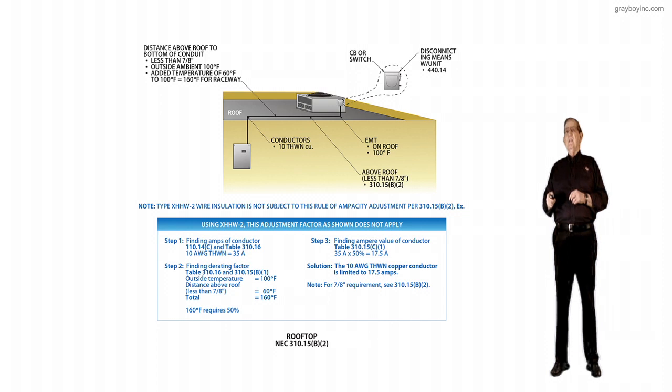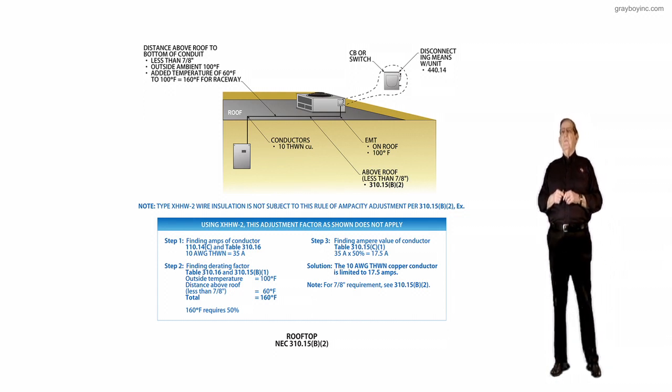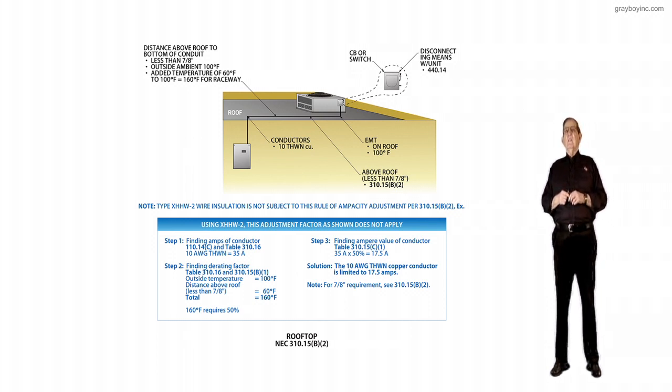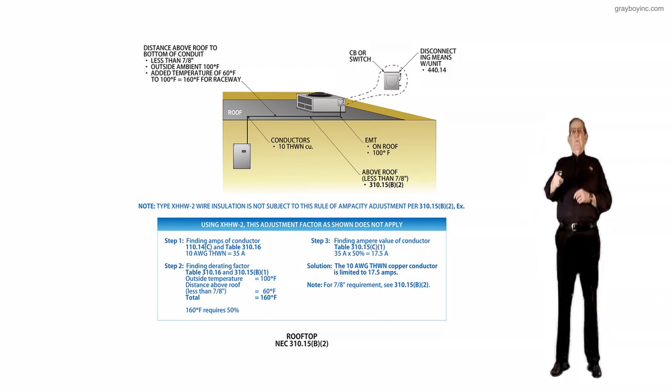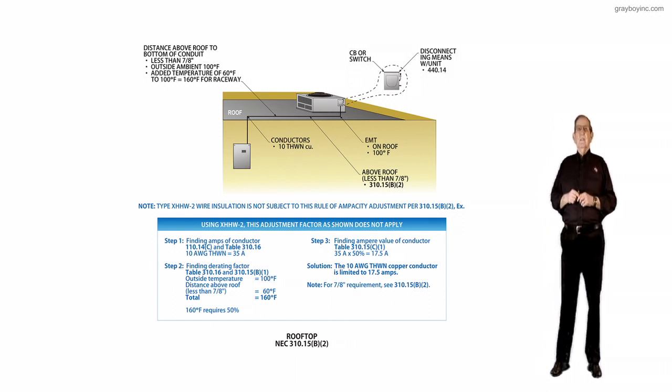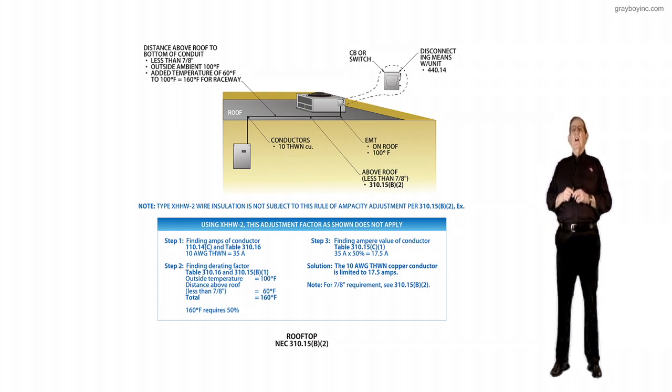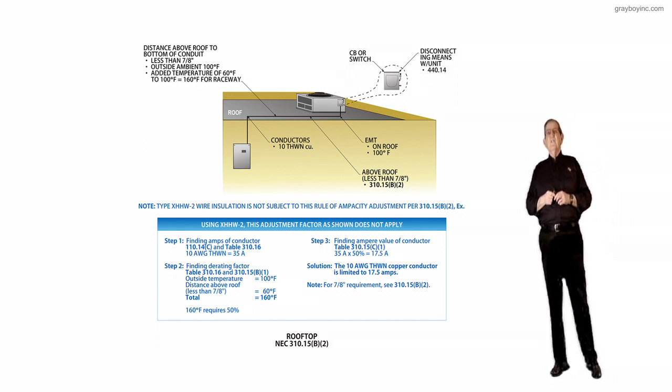Secondly, above the roof, if you're less than 7 eighths of an inch by this new code in 310.15B2, you're in the derating that you see in the calculation of the boxed-in information. If we look at the conduit and the top call-out, it says distance above roof to the bottom of the conduit is less than 7 eighths of an inch. The outside ambient temperature is 100 degrees Fahrenheit, and if that is the case, you've got to add on 60 degrees Fahrenheit. So you'd add that to 100 degrees Fahrenheit, you'd come up with 160 degrees Fahrenheit.